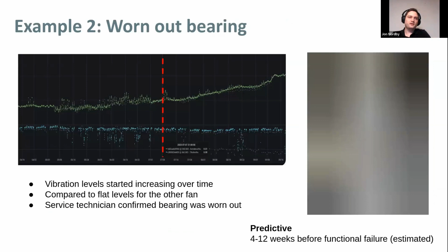Here's another example where vibration levels of a supply fan started to increase gradually and in an accelerating manner, after having been flat for many months prior. The service technician was sent after the alarm and confirmed the bearing was failing, scheduling a replacement a few weeks later when the part was available. This is a typical case of bearing wear-out, well known from literature and experience.